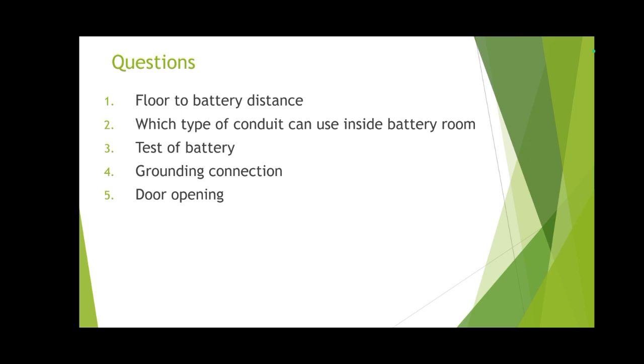Grounding connection — battery room door shall open outward, not inside the battery room. This is a very important question. Inside plants, battery rooms and substations are often connected to each other in the same area, but the battery room door shall not open inside the substation. The battery room door shall have a separate entrance and shall open outward.